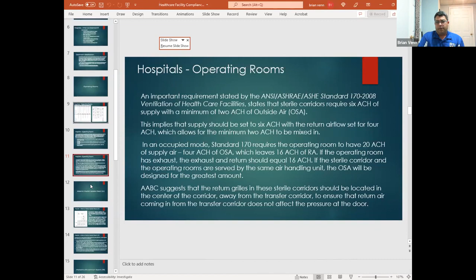I've only seen it asked for a few times, but we're trying to raise awareness of this because as the changing of the guard occurs and the facilitators are turning over, newer facilitators are digging more into these standards and trying to understand them and make sure that they're compliant. So again, a new thing to look for is a possible call for the outside air going into a room to be accounted for. And you have to capture the supply and the return air and make an inference of what the difference is, being the delta on outside air. I know that was a wordy slide. I hope I did it justice.